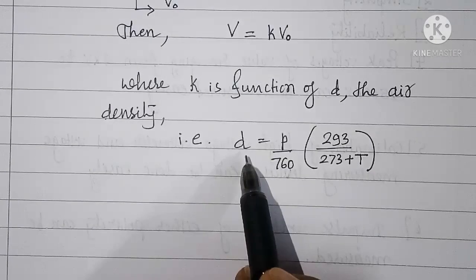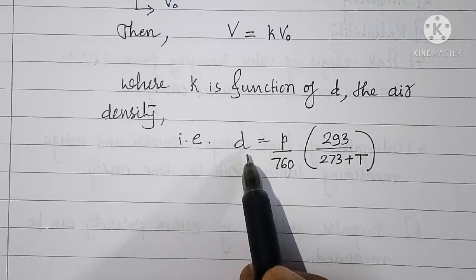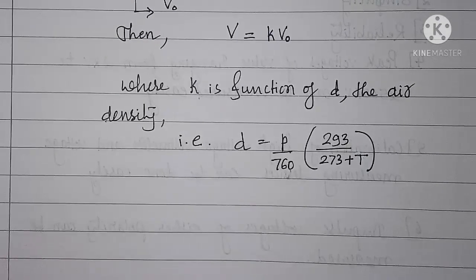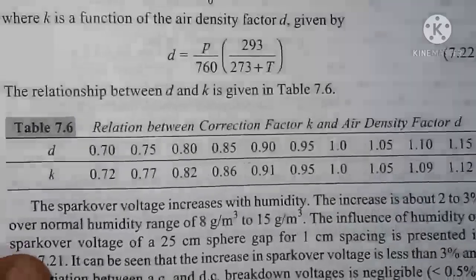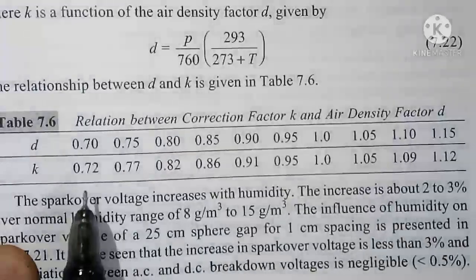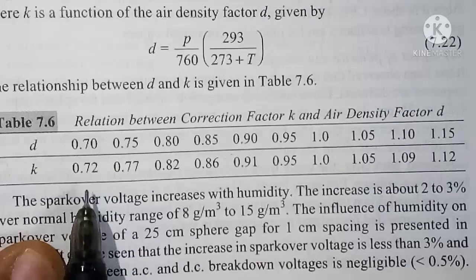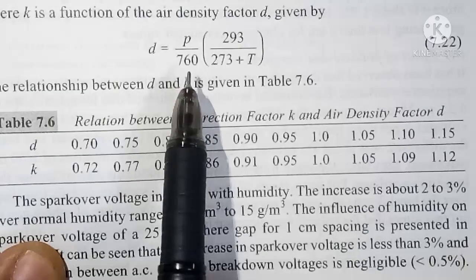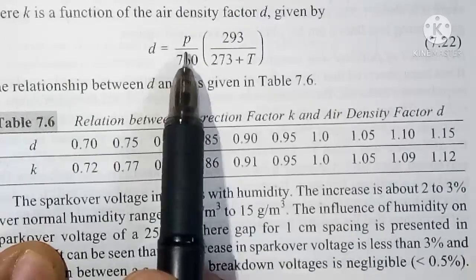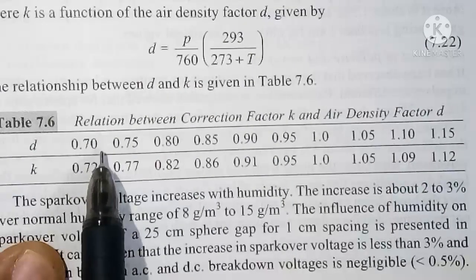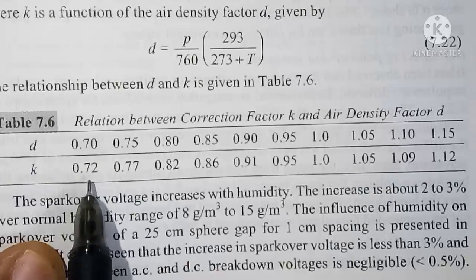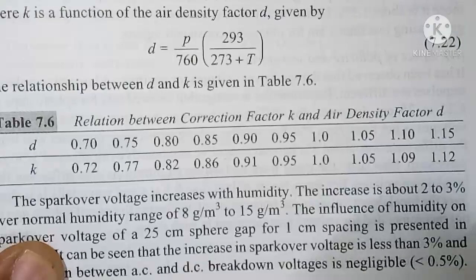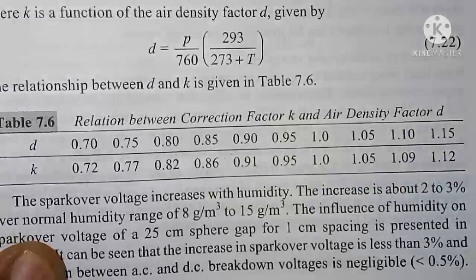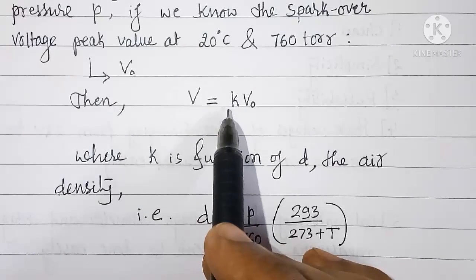Knowing P and T, we can calculate the D value, and if we calculate the D value, then we can know the value of K by referring to the chart that I am going to show you now. So here is the chart to which we have to refer to know the value of K. When we calculate the value of D using the values of P and T as 0.70, then the corresponding value of K is 0.72, and this we have to make use of to calculate the spark over peak value of the voltage V using this equation.